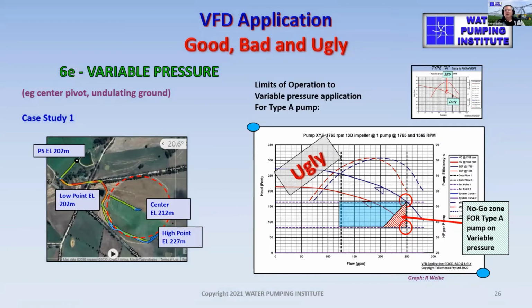So, you know, just looking at that last slide, if we consider an envelope of operation of the VFD, of pressure and flow, we would want to block out any pump that's operating in this zone if it is a type A pump. The type A pump is where the duty is to the right-hand side of the best efficiency point, and this is for a variable pressure situation.